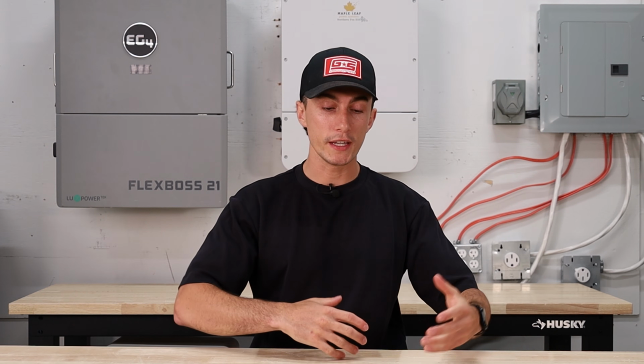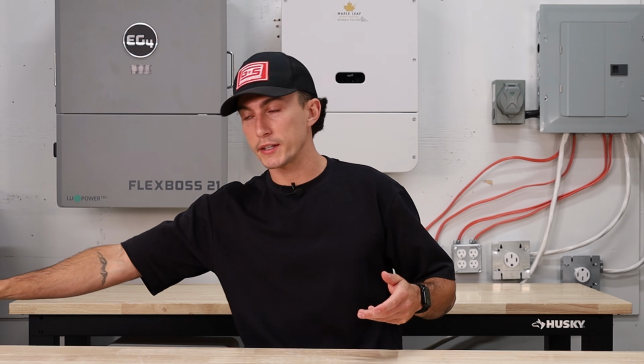Because you need a bigger cable to run a higher amperage, 48 volt systems tend to always have batteries really close to the inverter so you don't have a lot of voltage drop in that wire. The longer the distance power has to travel through a wire, the more it's going to drop by the time it gets where it's going.